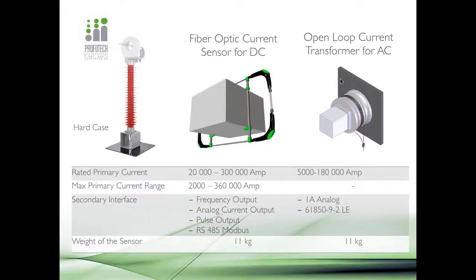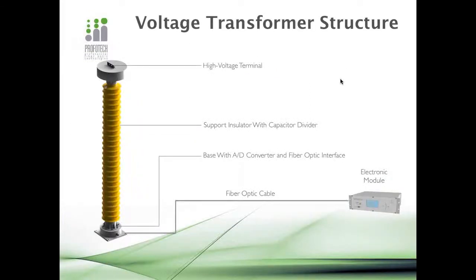The secondary interface of these two types of current sensors is, for the DC, frequency output, the analog current output, the pulse output, and RS485 Modbus protocol output. And for the AC current sensor, it's just a standard 1 amp analog output or IEC 61850-9-2 protocol interface. And the weight is really small compared to any kind of current transducer. It's only 11 kilos.